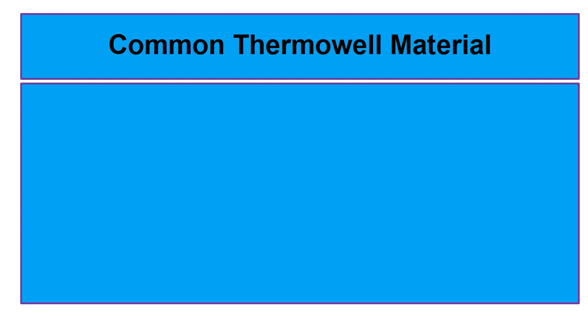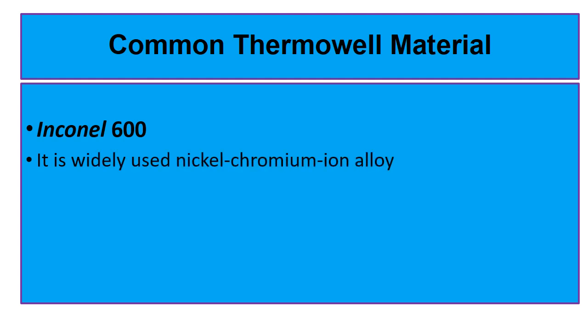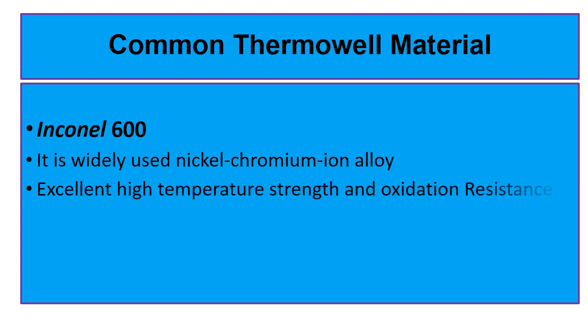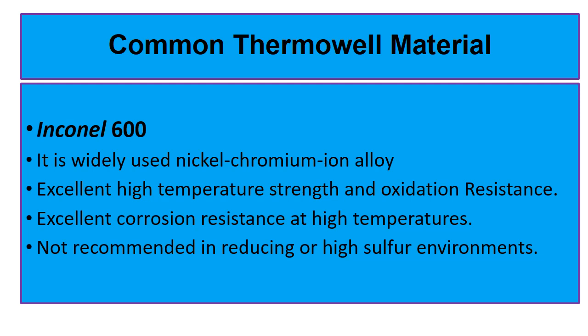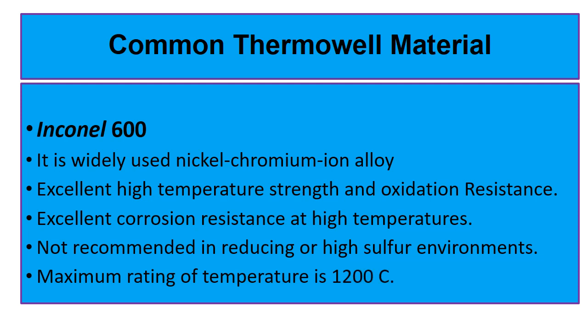The next material we are going to discuss is Inconel. Inconel has two grades. Inconel 600 is a widely used nickel-chromium-iron alloy with excellent high temperature strength and oxidation resistance. This alloy has excellent corrosion resistance at high temperature. It is not recommended for use in reducing or high sulfur environments. The maximum rated temperature is 1200 degrees centigrade.